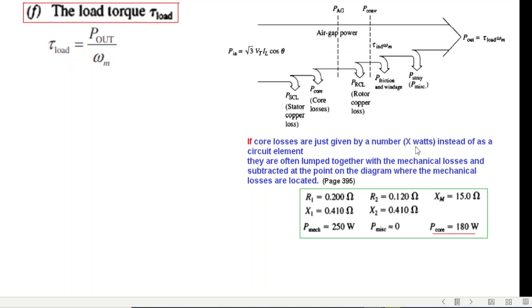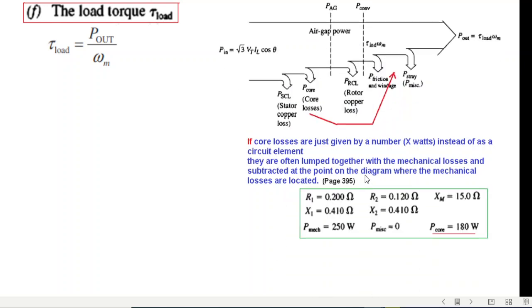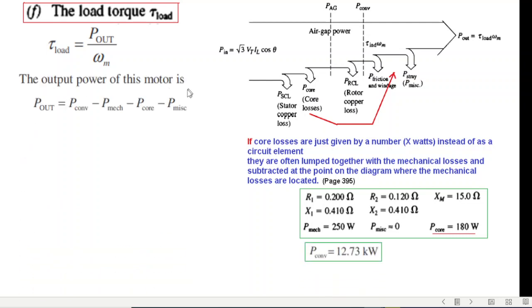Here is an important point. If core losses are given as a number of watts — for example, the core loss here is given as 180 watts — instead of as a circuit element (in our question X_m is given but R_m is not), then we lump the core loss together with the mechanical losses. So the total output power P_out equals P_converted minus P_mechanical minus P_core minus P_miscellaneous.